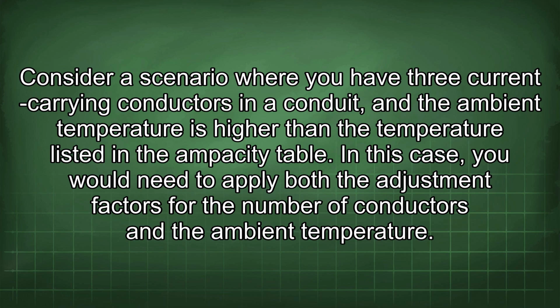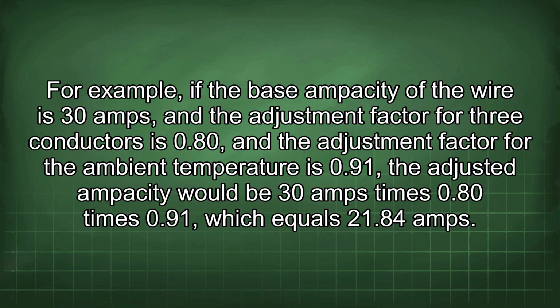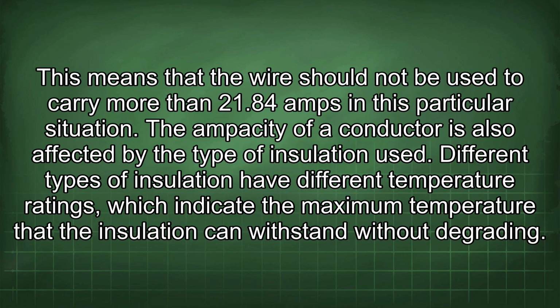In this case, you would need to apply both the adjustment factors for the number of conductors and the ambient temperature. For example, if the base ampacity of the wire is 30 amps, and the adjustment factor for 3 conductors is 0.80, and the adjustment factor for the ambient temperature is 0.91, the adjusted ampacity would be 30 amps times 0.80 times 0.91, which equals 21.84 amps. This means that the wire should not be used to carry more than 21.84 amps in this particular situation.